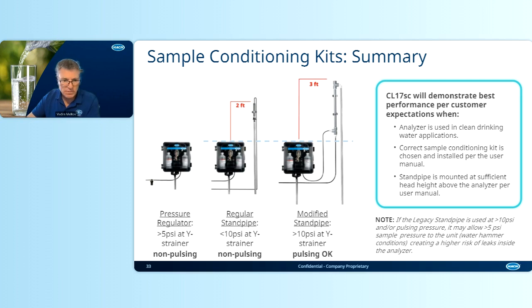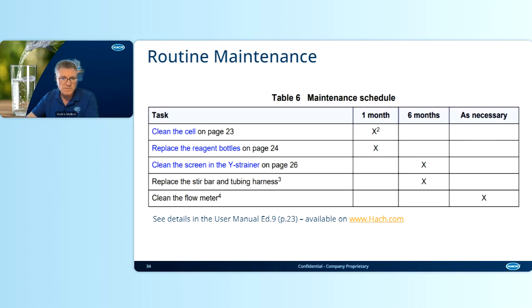If you have a pump, then some pumps provide pulsing pressure and sometimes create a water hammer inside the analyzer. That is very detrimental because it can blow off the tubing and flood the analyzer. We don't want that. So in those situations, the modified standpipe kit, which provides a different flow path, can be used at above 10 psi and with pumps providing pulsing pressure. Those things need to be absolutely taken into account, and then the instrument will perform perfectly fine, and the maintenance will be confined only to this routine schedule, which calls for cleaning the cell.